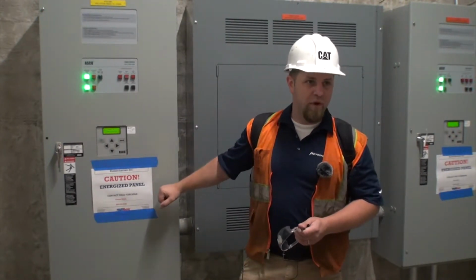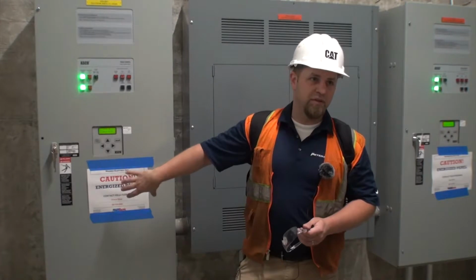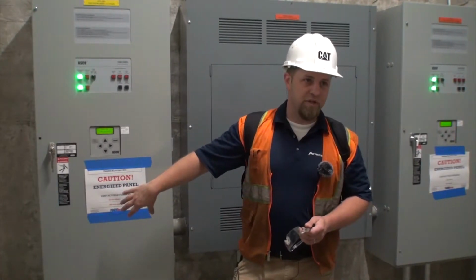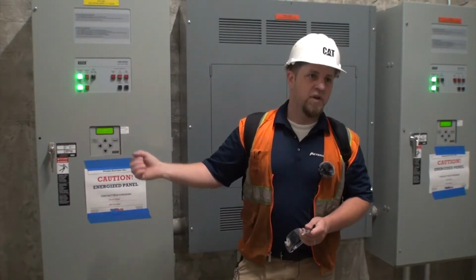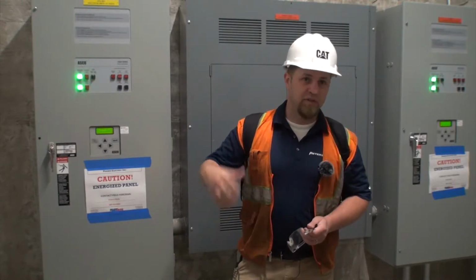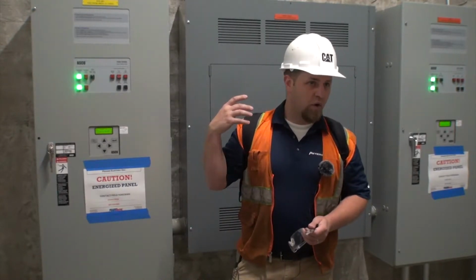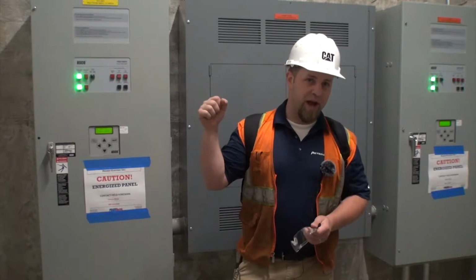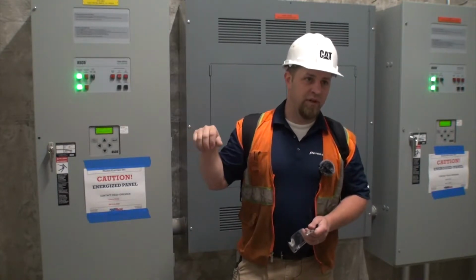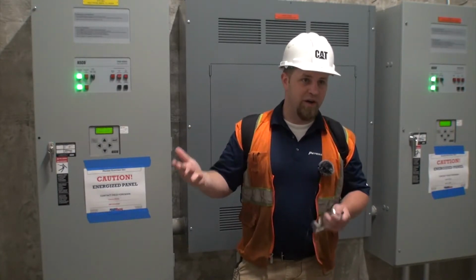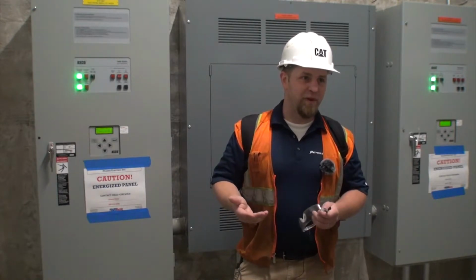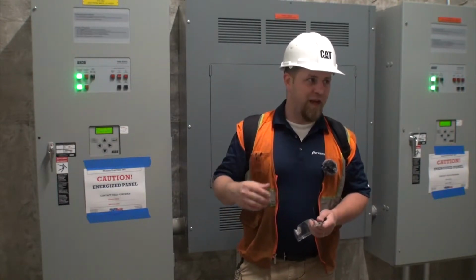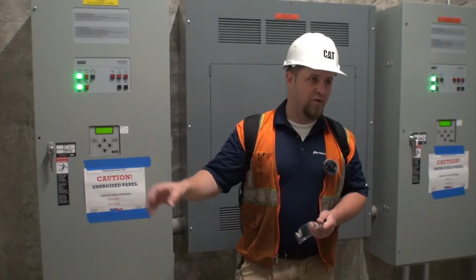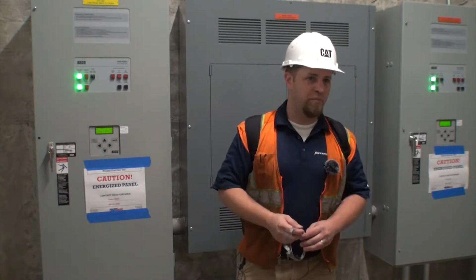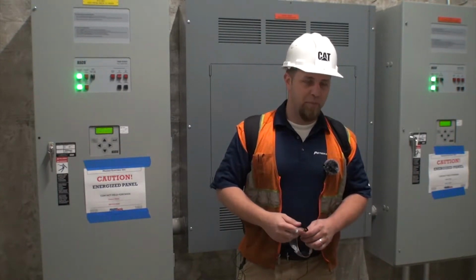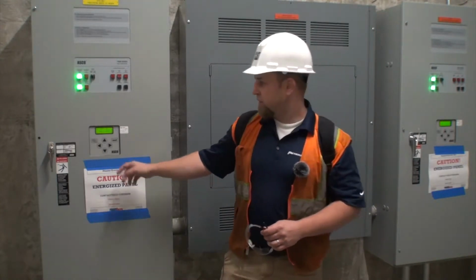It's better to do it from here, because if this fails, you're not having to call an electrician. You can just open it up, do a manual transfer, start up the generator and run on that, or transfer back to utility manually and get back up and running one way or another. The difference is significant on a bad day versus calling an electrician out for a big shutdown, big permits, big money, compared to just doing your transfer once a month from here.